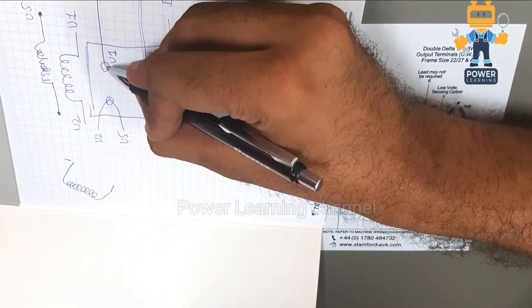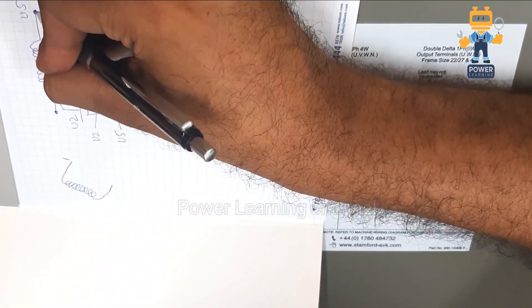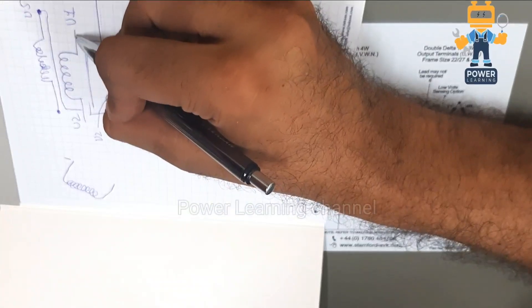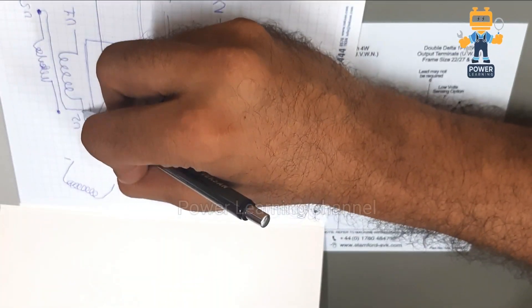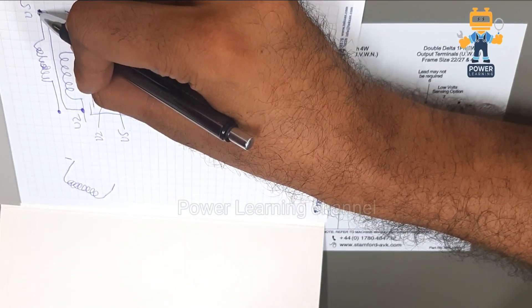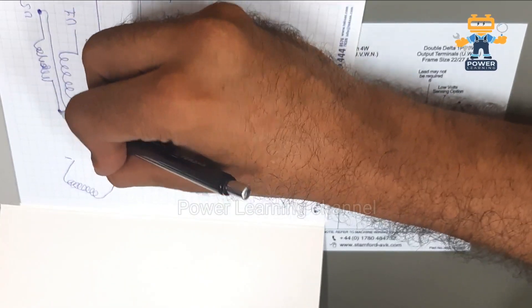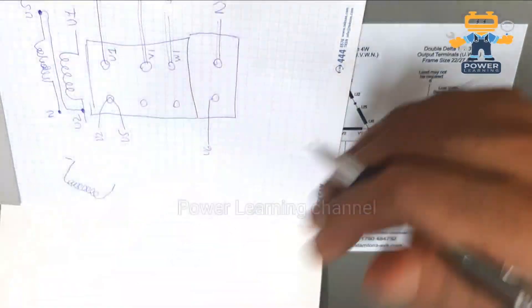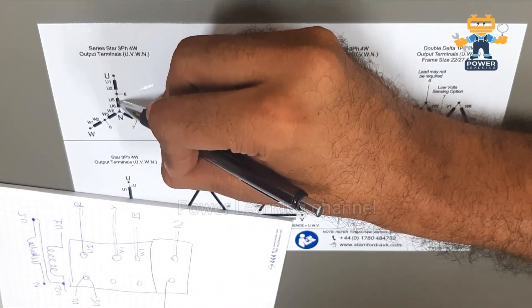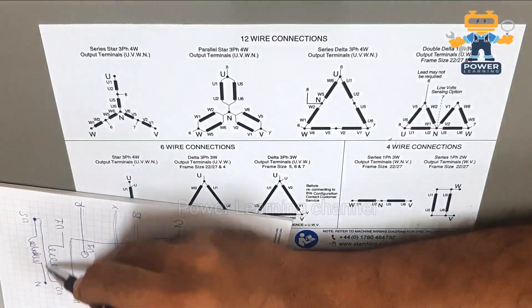Now see: u1 is connected with the start of the first coil, u2 is the end of that coil, and u2 is then connected with u5. This wire runs from u2 to u5, so the coils are in series — starting from u1, going through u2 to u5, then out from u6 to neutral. This is end-to-end series connection.